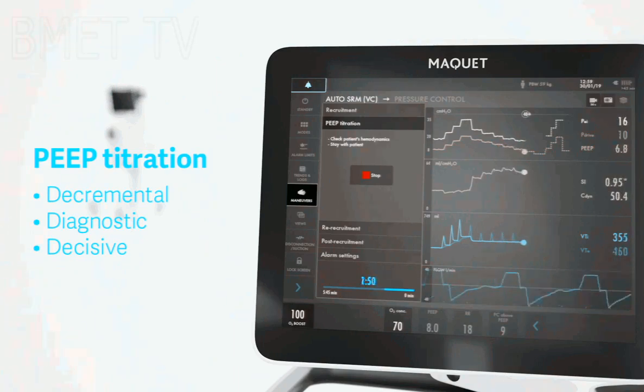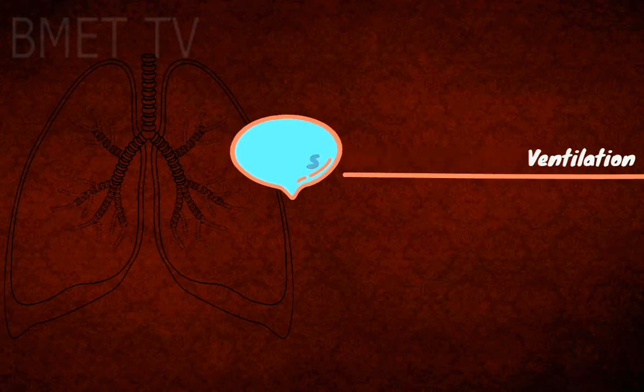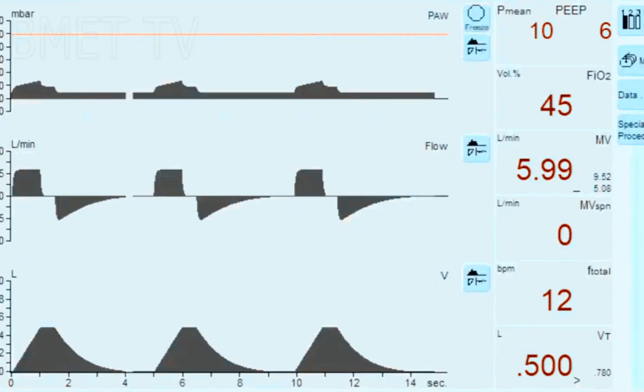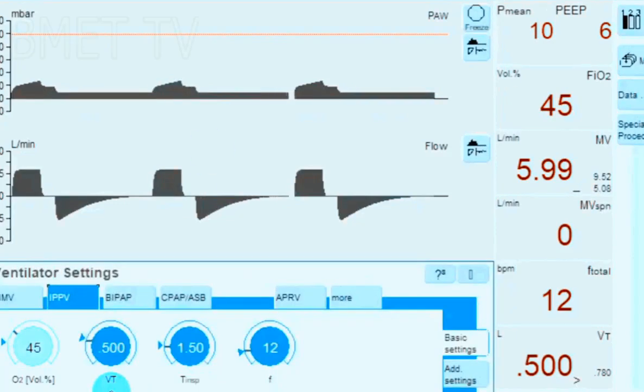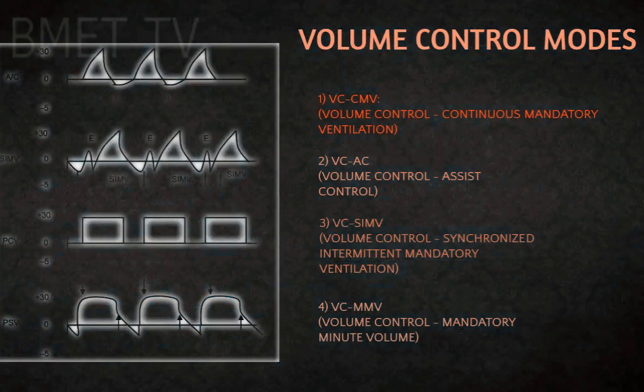Let's know about different ventilation methods. Let's begin with volume-controlled ventilation. During volume-controlled ventilation, the set tidal volume is supplied by the ventilator at a constant flow. The inspiratory pressure is the resulting variable and changes dependent on the changing lung mechanics. Volume-controlled ventilation has different modes. They are as follows: volume control, continuous mandatory ventilation; volume control, assist control; volume control, synchronized intermittent mandatory ventilation; volume control, mandatory minute volume.